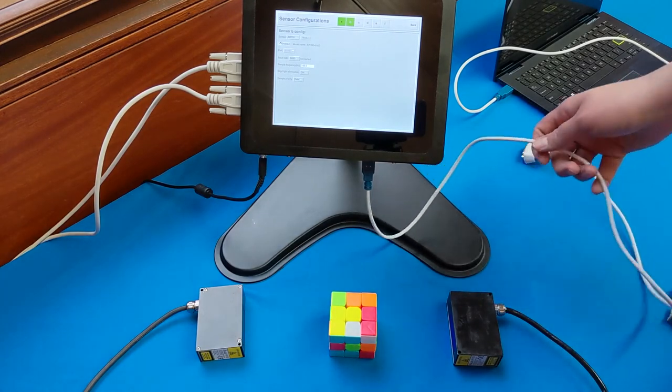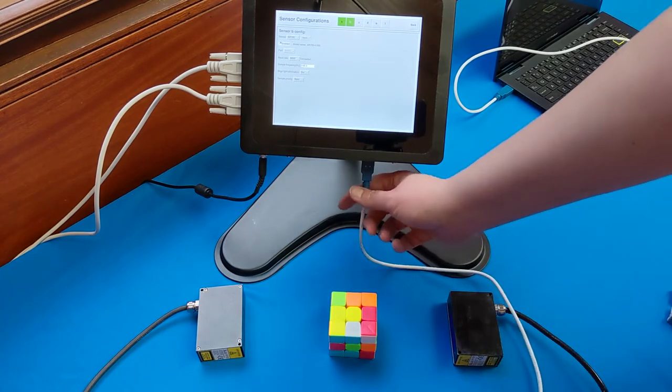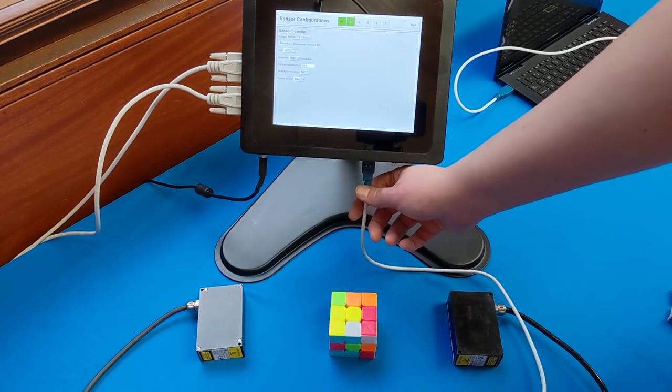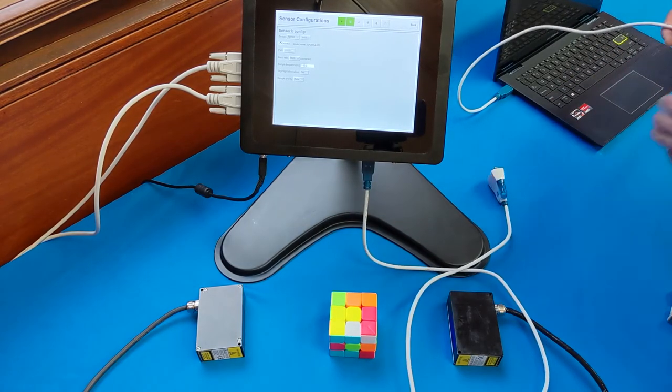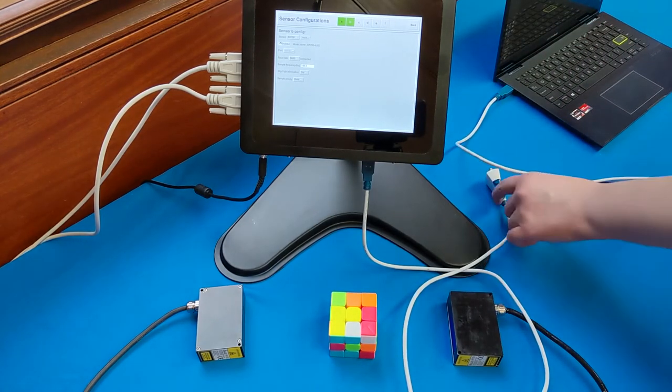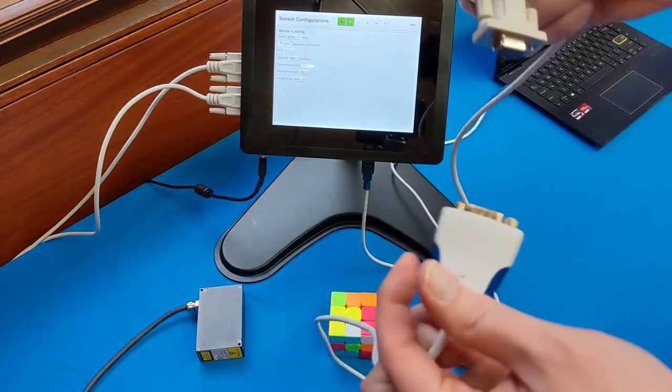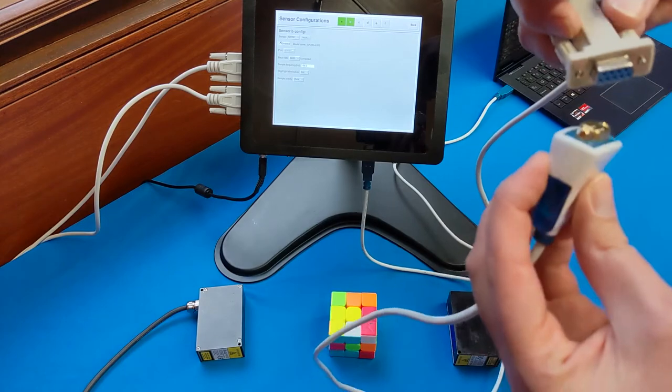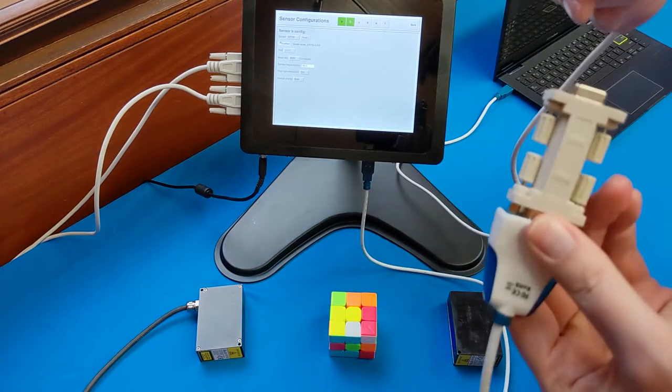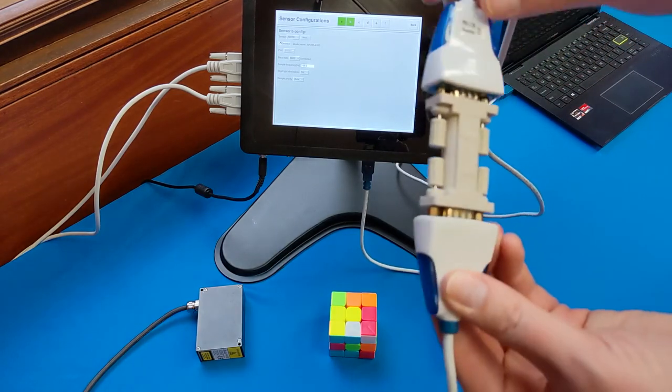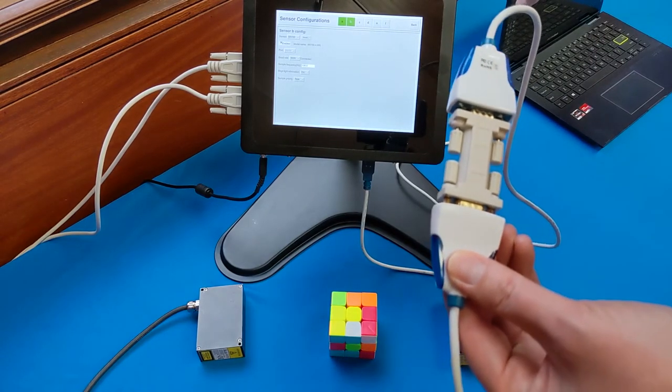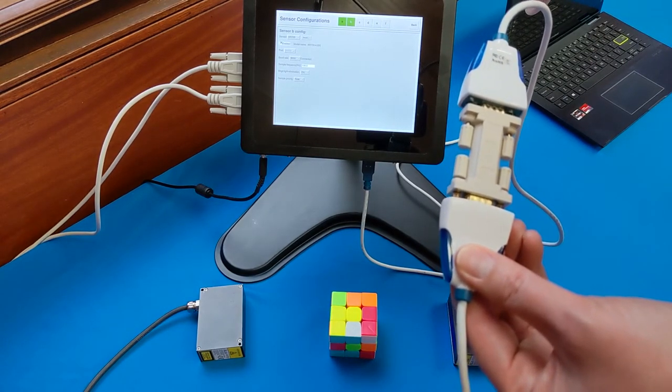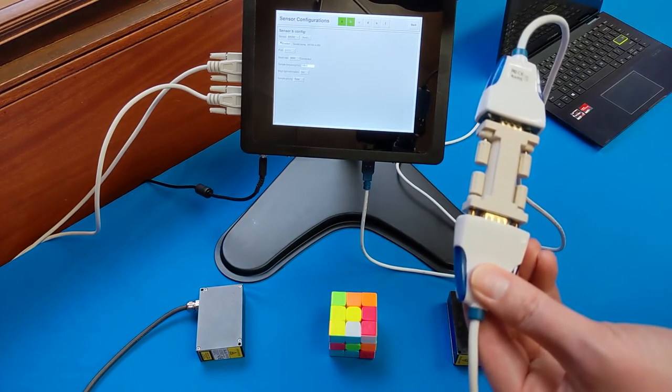You also want to have a serial to USB connector connected directly to any one of the USB ports in the touch panel. The other one you want connected directly to your computer. And then between them, you want to connect them both with a null modem. And what this does is simply reverse the transmission and receive wires between it. So what's transmission, what the wires for transmission on your computer is being received on the touch panel and vice versa.